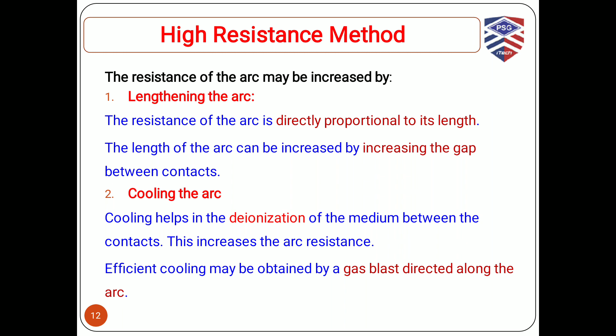This obviously increases arc resistance. So an effective cooling method can be implemented in order to initiate the deionization. It can be obtained by either a gas blast directed along the arc, or any other method by which you can cool the arc. So the cooling of the arc helps us in improving the deionization. That is, we try to interrupt the arc by deionization of the medium between the circuit breaker contacts.